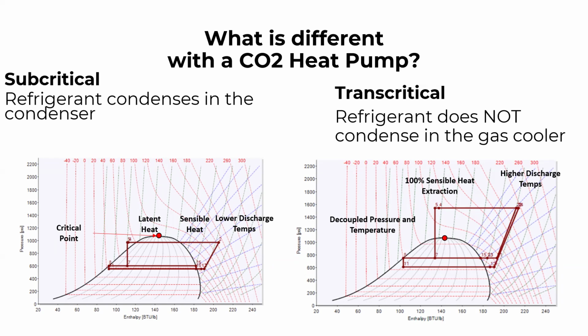If we're going to do something better, a transcritical system has unique, innovative technology aspects. One is you can make high discharge temperatures and do supplemental heating. You can do heating and take 100% sensible heat extraction from the environment, using up to 140% more of that heat than traditional systems. You can also decouple temperature and pressure and do really wonderful optimizations—whether optimizing for cold, for hot, or somewhere in between, even at the same time. We can really dial that in.